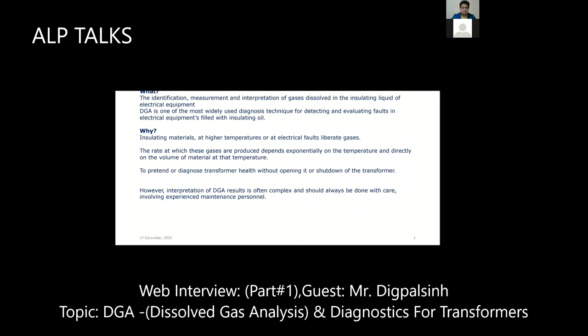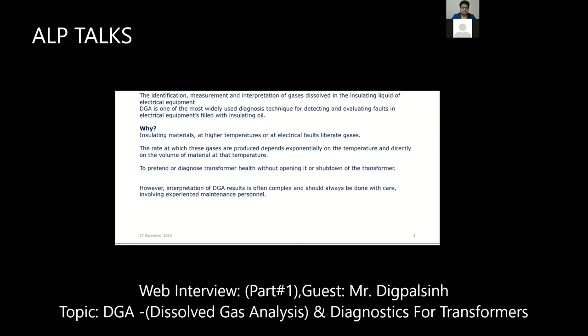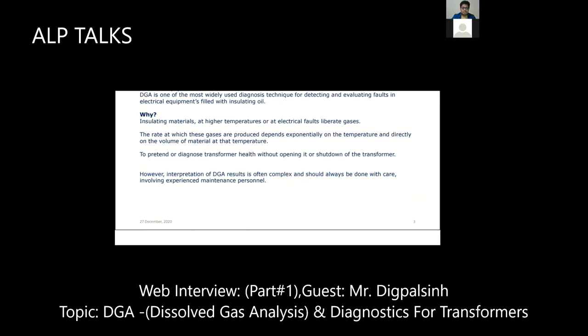Then why is dissolved gas analysis necessary? See, in every insulating material like mineral oil, paper, pressboard, thermally upgraded kraft paper, Nomex tape, at higher temperature, in a mineral oil or any natural or synthetic oil, they form or liberate some gases. The rate of gases produced depends exponentially on the temperature and directly on the volume of the material: how many liters of oil you have used, how many kg of the other insulating material inside the transformer. Actually, DGA applies to every electrical equipment filled with insulating oil, but today we will only discuss transformers. This is the reason why we go for the DGA.